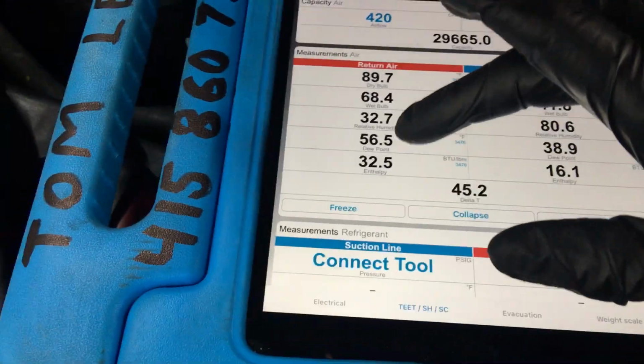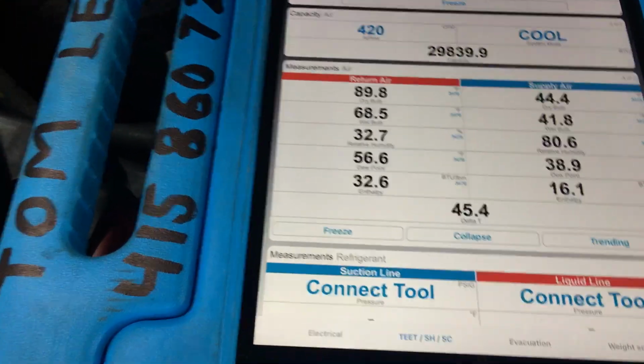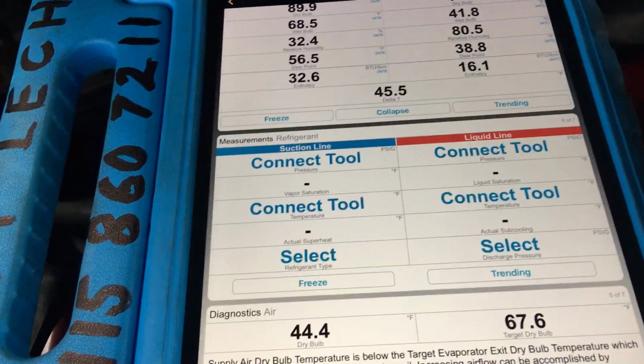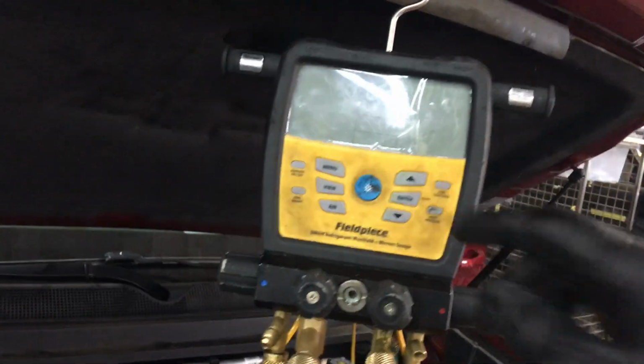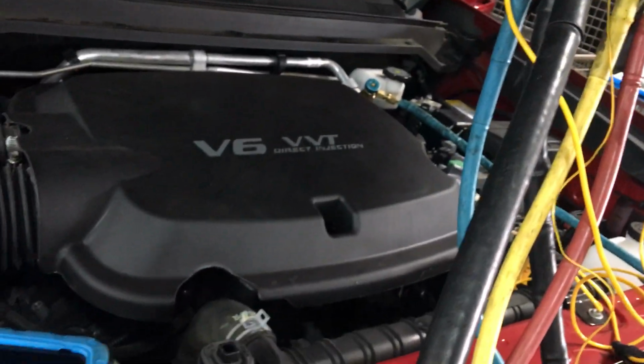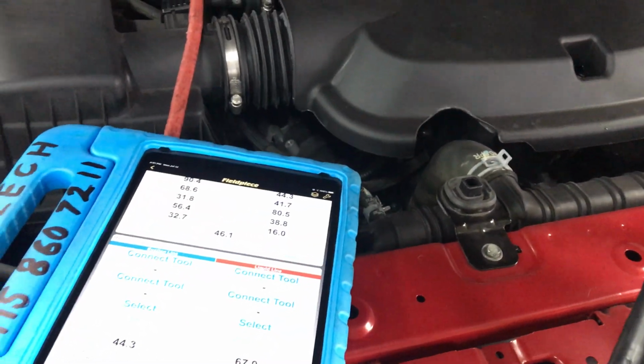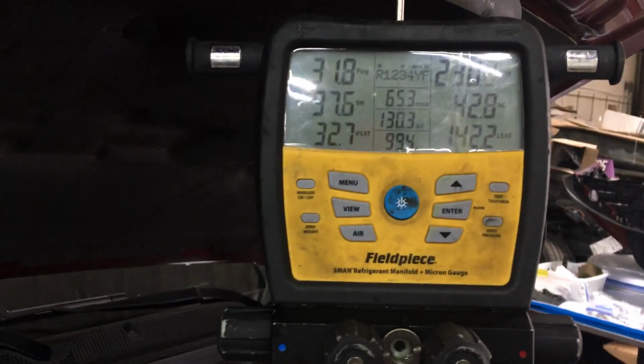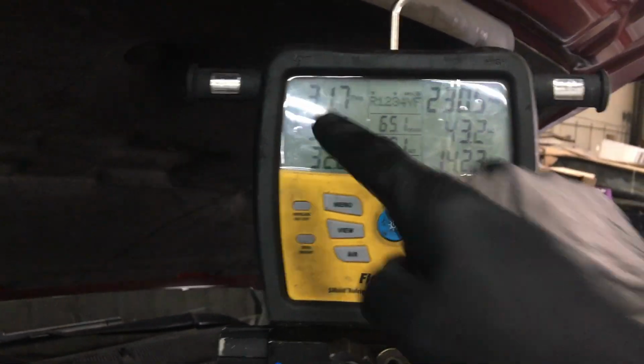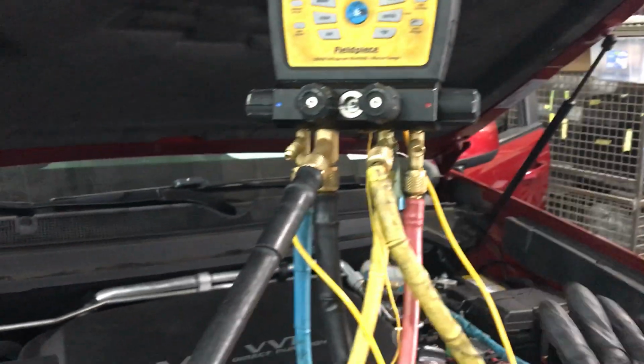So if you were trying to read, where's my gauge? Way down there on the suction line, you get this half-assed, oh, where the hell did it go? Lost connection. Oh, it shut off. Timed out. I've been on so long. But you see why it's almost 60 superheat, because of that internal heat exchanger. Oh, now we're 97 superheat. Oh my God. And this is what the factory designed it to be. It operates like this. It's the way it's manufactured.